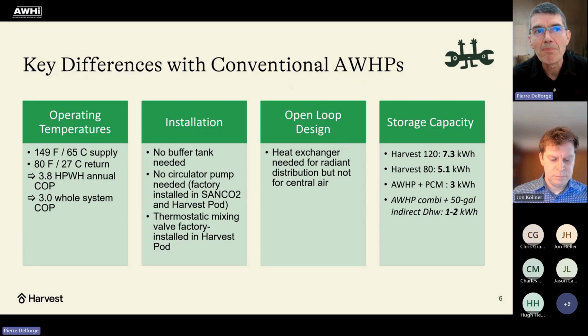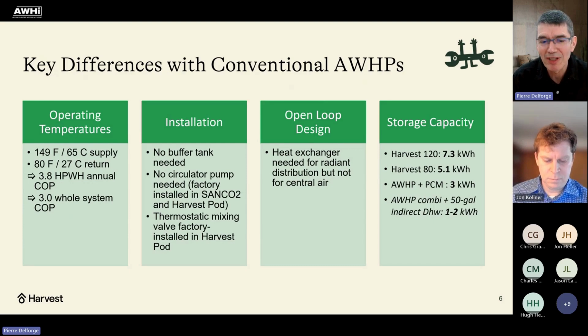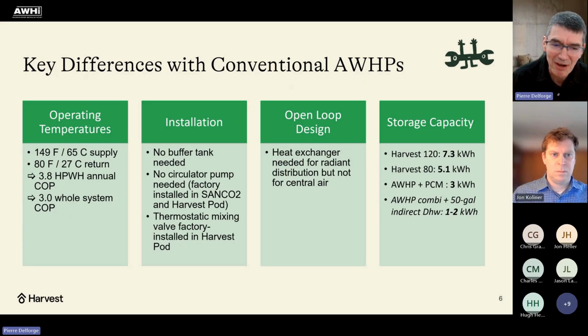Yeah, it varies a lot by home, but what we actually see in single family homes is about 20% domestic hot water and 80% space heating. In multifamily homes, it's either more balanced or sometimes higher domestic hot water. But in single family homes, space heating typically dominates as the majority of the heat output. Water heating load depends on the home again, but it might be somewhere around 30 to 40,000 BTUs a day. The SANCO2 has a capacity of about 300,000 BTUs a day. So if the SANCO2 were running 24 hours a day, which is not the goal and doesn't happen very often, the maximum capacity is 300,000, and domestic hot water is only about 10% of that.